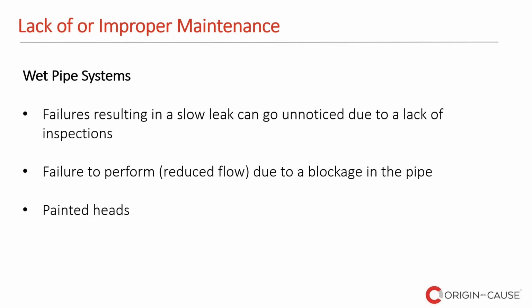And a very typical issue is the heads get painted. When a head gets painted, it increases its activation time, so it reduces its performance. And you can have a fire that spreads beyond what it should have, and then we can look at that as well and determine whether someone should have been inspecting those heads and found the issue beforehand and prevented the additional damages that result from that.